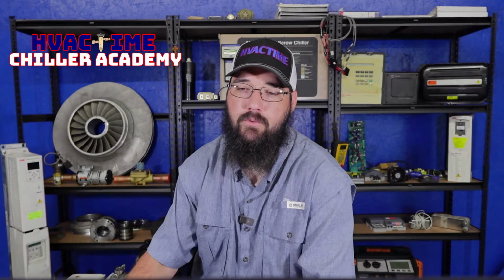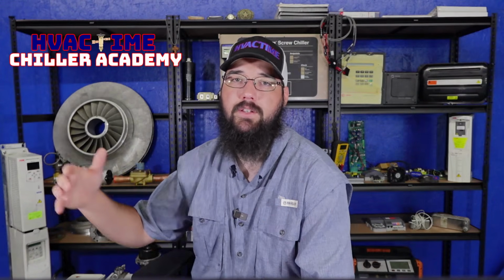Yeah, that's what it boils down to. And being 18 CFM versus say 12 or 16 or 18, by the time we get into these ranges, the CFM matters a lot less to me than the actual hoses and the configuration of what I can hook up to. Once I break over 12, I really don't care that much how much CFM the pump can do, because getting my hoses to perform at even just 12, much less above that, is part of the main challenge. I've got to get my hose assembly set up to where I can even handle that much CFM. And there's only going to be that much CFM at the upper end of the pull down. As we get into the deeper parts of the pull down, we're just not moving that same volume anymore. So the bigger CFM pump isn't necessarily always better.